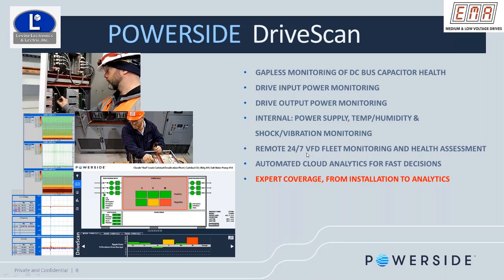We offer what is known as fleet monitoring 24/7. By the way, every monitoring that we do is 24/7 by the drive scan. It never rests, right? Like a person, this thing is always running and trending, taking data for us, and can store up to 2 years worth of data on the drive scan itself. And then we have an automated cloud analytic part of the drive scan, wherein we can look at a significant amount of drives and summarize the health of the drive by using green, yellow, and red. But if you have, for example, 100 VFDs, and I'll go into details more, it's very hard to monitor and determine, look at all those reports that we get from drive scan.